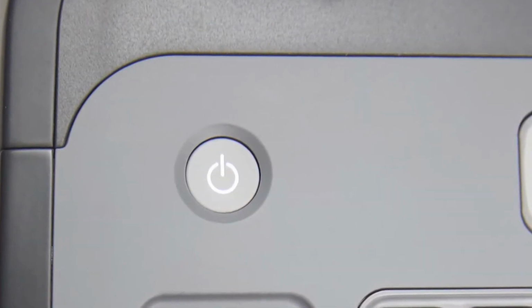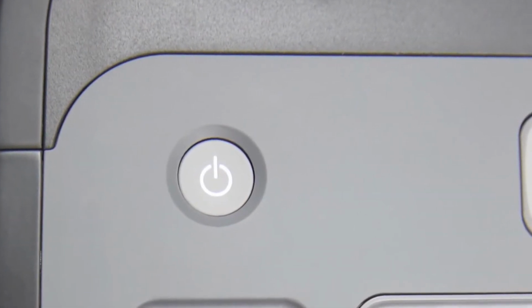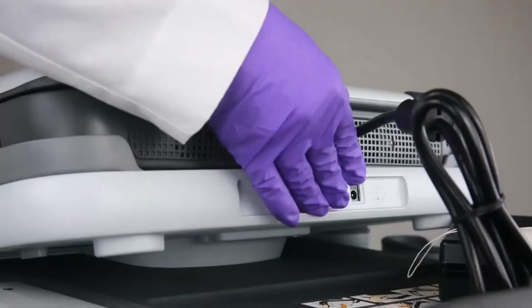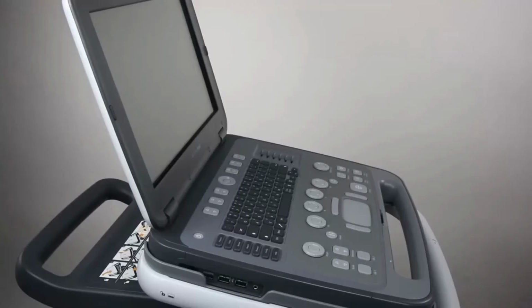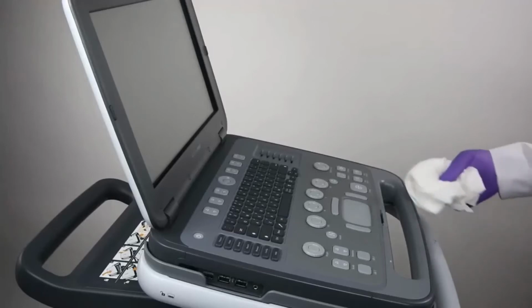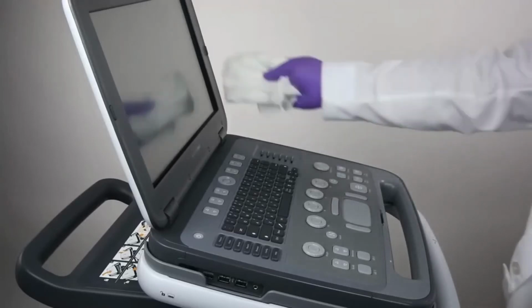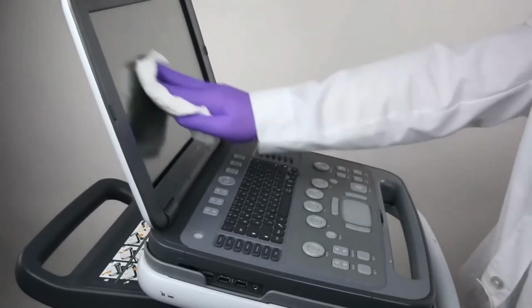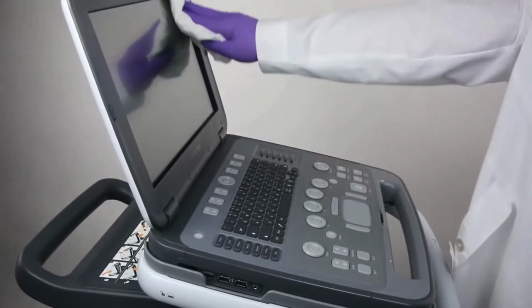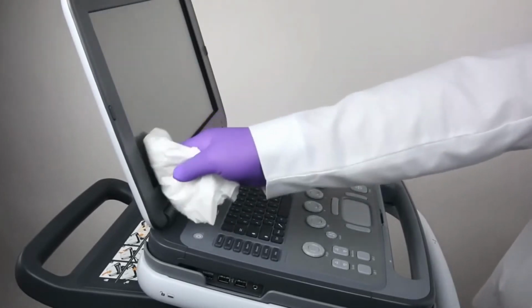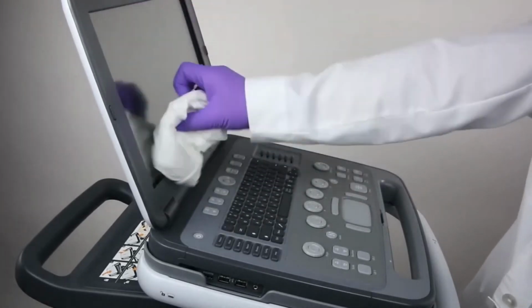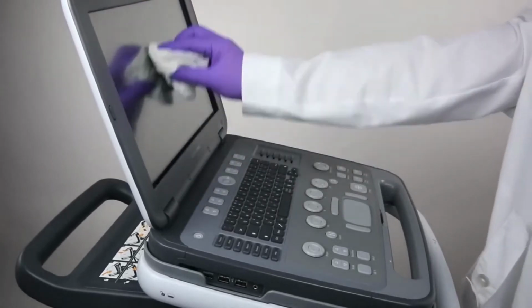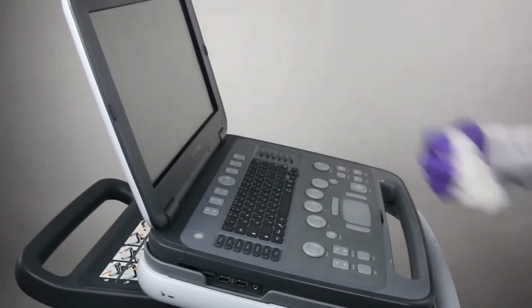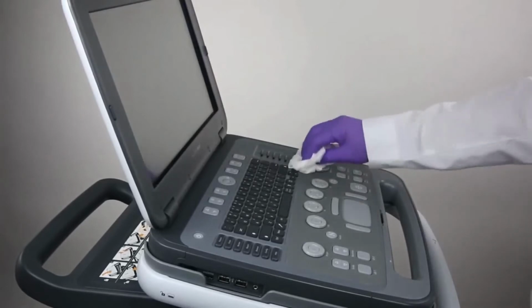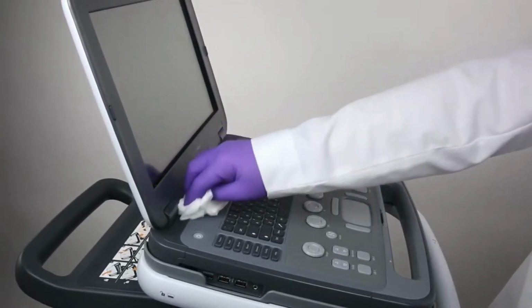The first step to cleaning the Acuson P500 system is to power off the system and unplug the power cord. Lightly moisten a clean gauze pad or lint-free cloth with mild detergent or an approved disinfectant. When cleaning the touchscreen, use only mild detergent or water. Applying disinfectant to the touchscreen may damage the surface. For a list of approved cleaning and disinfectant agents, refer to the user manual.